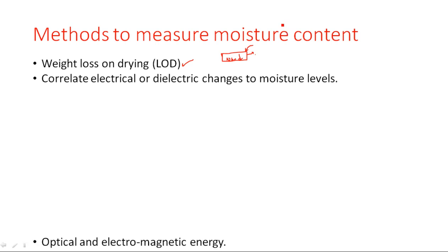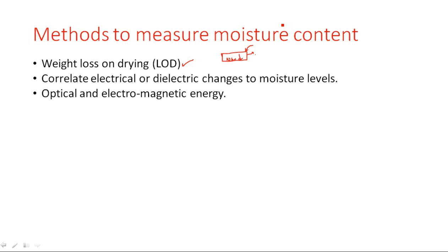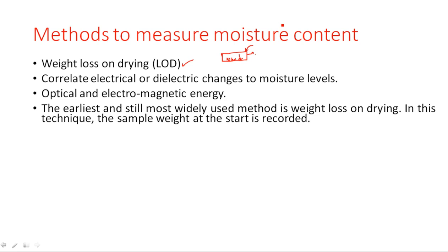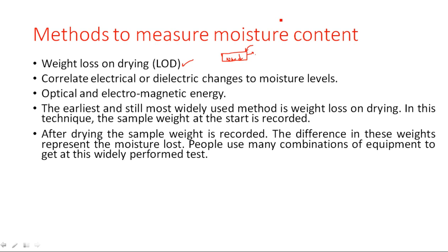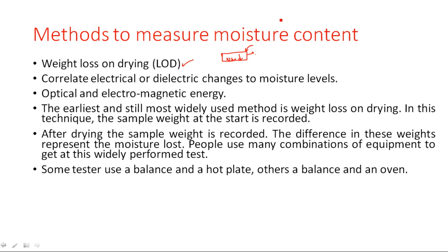The earliest and still most widely used method is weight loss on drying. In this technique, the sample weight at the start is recorded, then after drying the weight is noted again. The weight difference between these two represents the moisture lost. People use many combinations of equipment for this test — some use a balance and a hot plate, others use a balance and an oven.